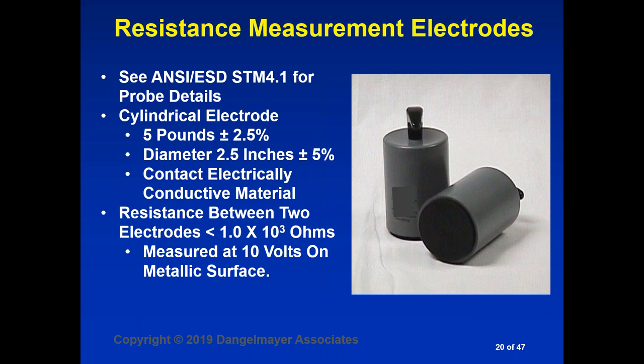The other measurement that's a real good thing to do is an open circuit measurement on your tester to make sure that when nothing is connected to it, or the electrodes are not placed on a surface, that it does measure an open circuit. Very often you'll find that there's something wrong with an instrument that measures lower resistances, even though there's no electrodes connected to it. So a short circuit measurement on a metal surface, an open circuit measurement, two of the things to verify the measurement instrumentation is working correctly.